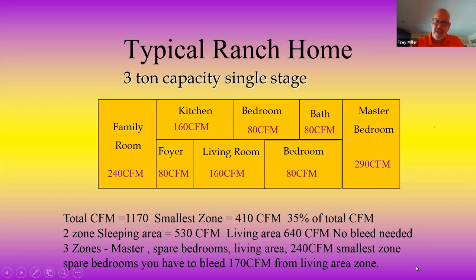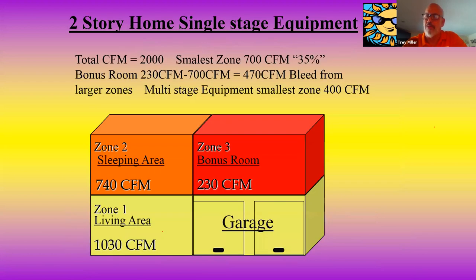Okay. Now let's look at the real hard one. The hard one here, the two-story home, 5-ton unit, room above the garage with an 8-inch run, 230 CFM. Well, total CFM in the system is 2,000. Smallest zone in the home is 230. My smallest zone that I can have at 35% of the 2,000 is 700. Okay? Subtract the 230 from the 700, which gives me 470 CFM of bleed from the larger zones. I'd probably split 270 upstairs, 200 downstairs.